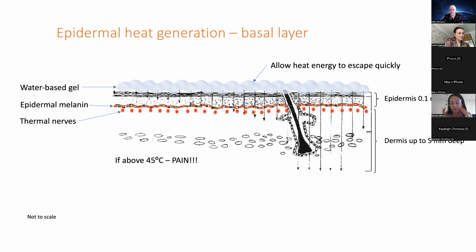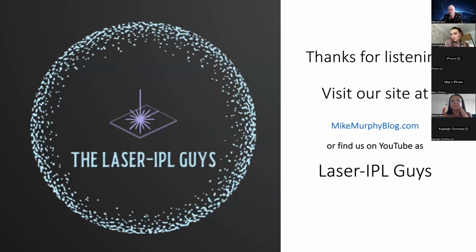When you talk about 5,000 watts or 1,000 watts, you are talking about end-piece watts, correct? At the skin, yes. Okay. Yeah, that's a good point too, and this just adds to the confusion. You can look at these machines, and on the back they should have a boilerplate which gives you all the data, and says 2,100 or 3,000, but it's the total energy of the machine with the power supplies and everything. Precisely. So what's important is the fluence or the energy you have in the handpiece. And that could be completely different. Yeah, of course.